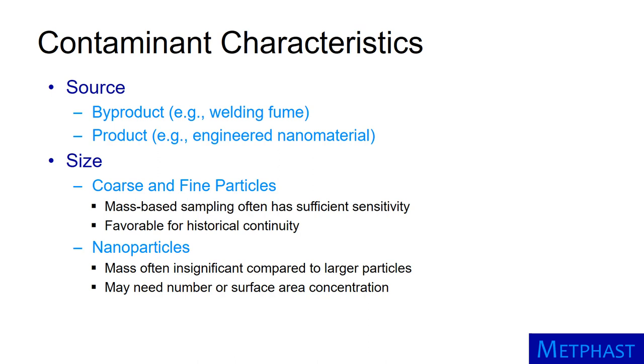We also need to know the particle size range we are interested in. For coarse and fine particles, mass-based sampling often has enough sensitivity for detection because these particles have sufficient mass to weigh. Gravimetric sampling is favorable because of historical continuity to past measurements. In contrast, other types of instruments are often needed because the mass of nanoparticles is insignificant compared to larger particles. In this case, we either need new samplers to collect nanoparticles alone, or instruments that measure number or surface area concentration.